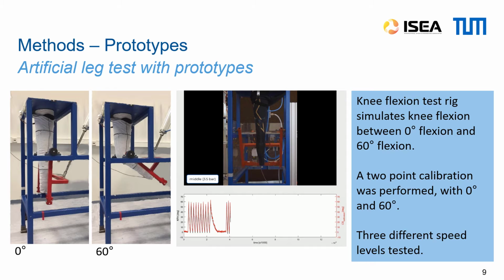For the validation test, single leg prototypes were used. On a knee flexion test rig, the prototype was tested for functionality. The custom-made test rig consists of an upper leg and a lower leg made of silicone connected by a hinge joint. A pneumatic cylinder powered flexion and extension movement in the range of 0 to 60 degrees. The velocity of the flexion extension movement was varied by controlling the air pressure that supplies the cylinder.